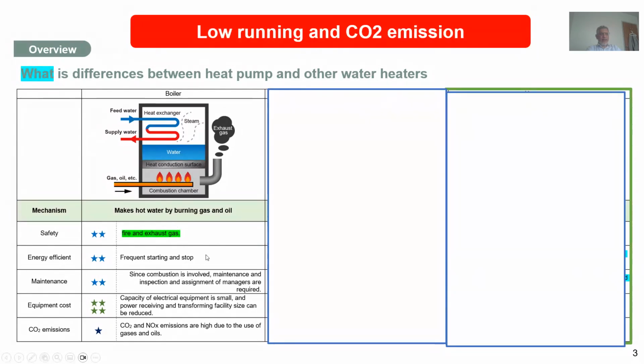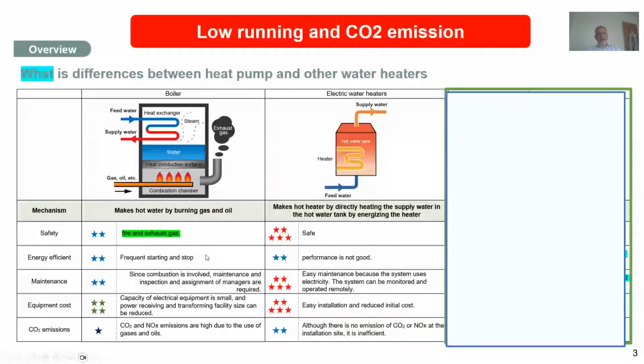If you move to the alternate solution, hot water using electric heating, yes, it is good because there is no gas, so safety is not much of an issue. If you're using electric heaters, you can do 100% max efficiency. Again, if you're giving a star rating for efficiency, you end up with a two-star rating for electric heating. Installation is easy because there is no gas fitting involved.